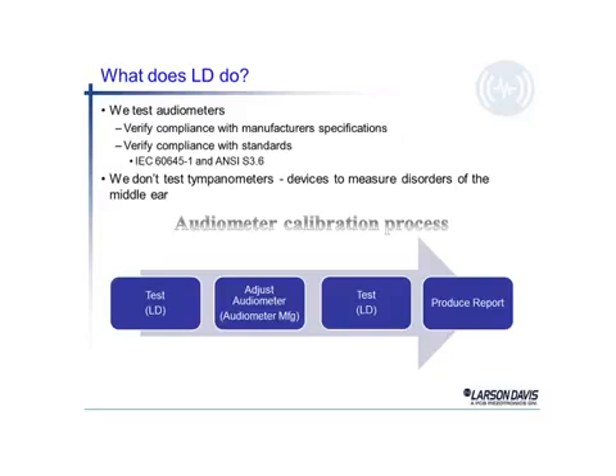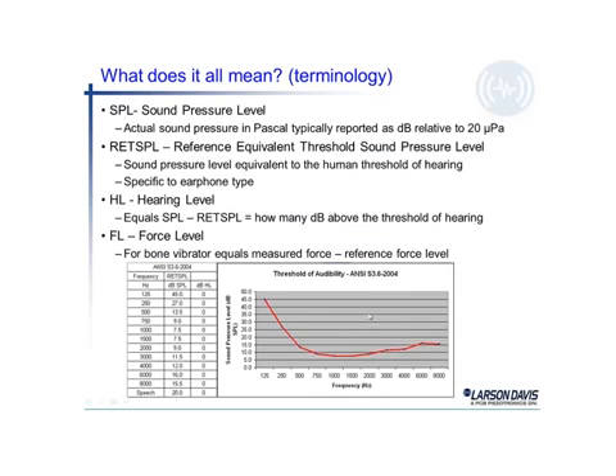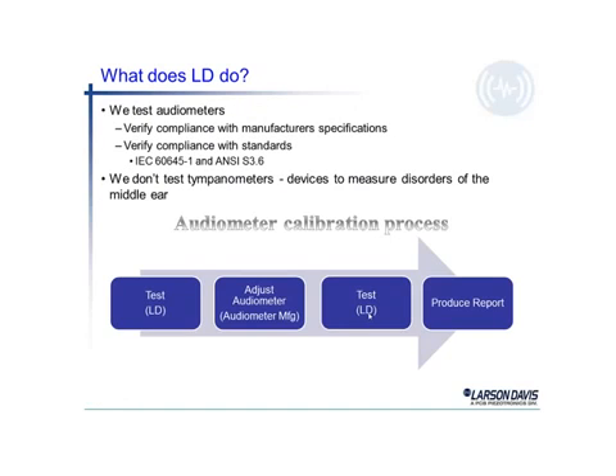The calibration process then, LD does the test. If a fault is found, the audiometer is adjusted, perhaps even sent back to the audiometer manufacturer. Then again it's tested, and you can produce a report using the Larson-Davis equipment.